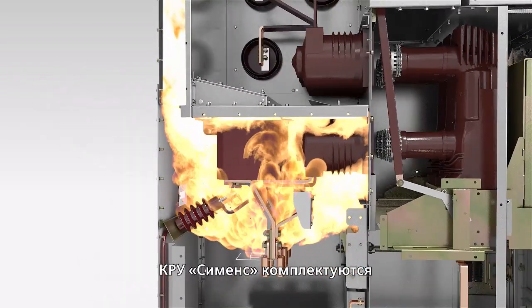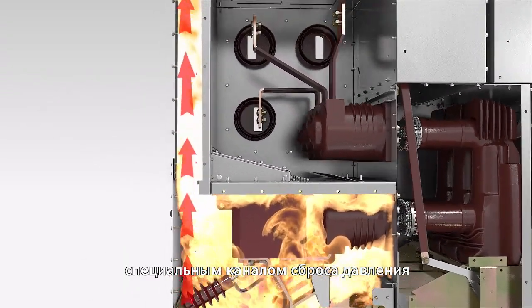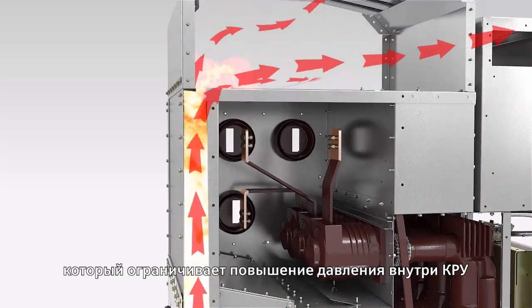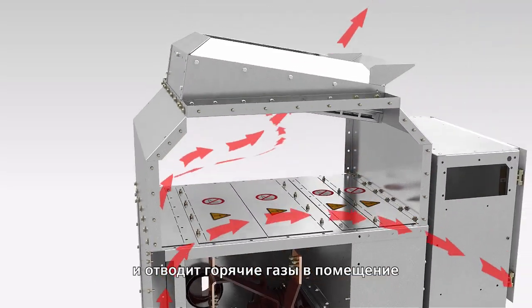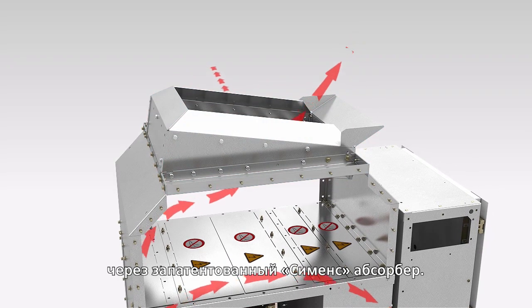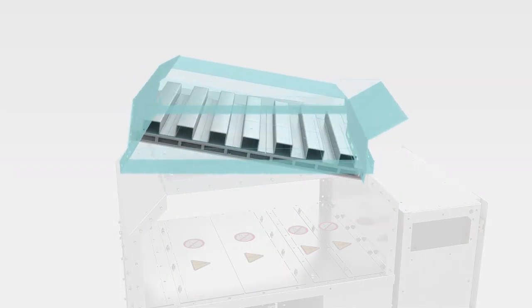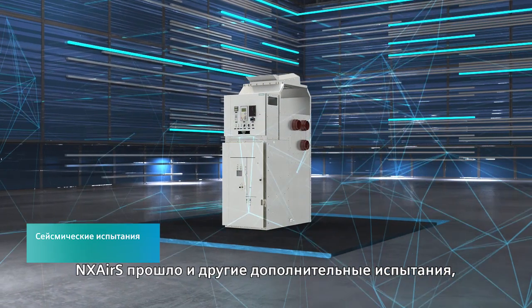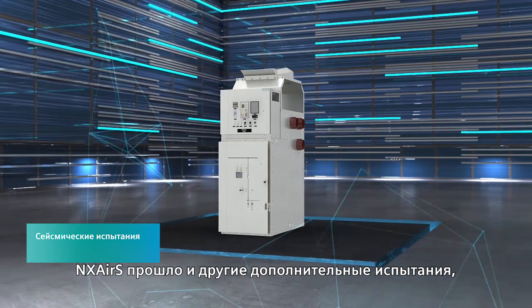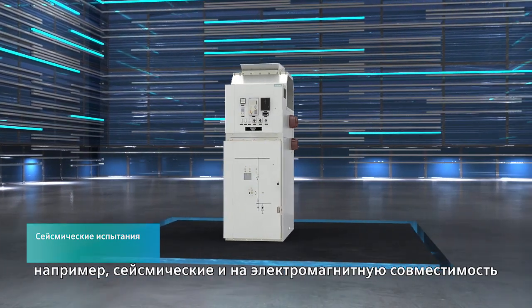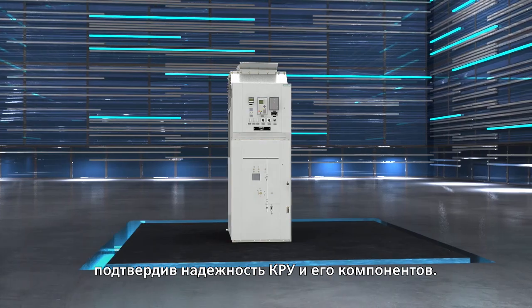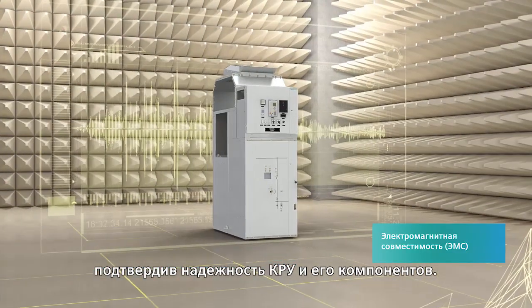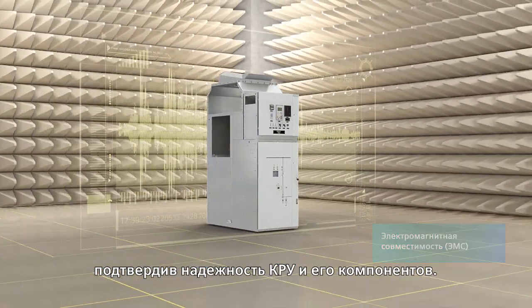To mitigate the effect of an internal arc, Siemens switchgears have a specially designed pressure relief channel to limit the pressure increase inside the switchgear and relieve the hot gases into the room via Siemens patented absorber. Besides standard type tests, NXAirS passes additional verification tests such as seismic and electromagnetic compatibility to prove reliable operation of the switchgear and installed components.